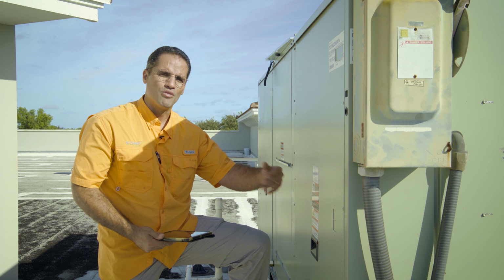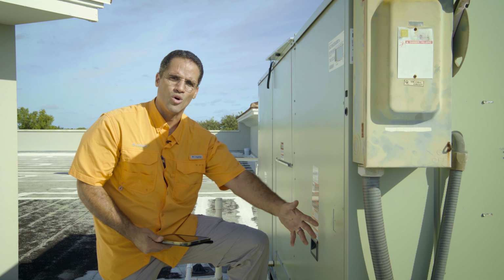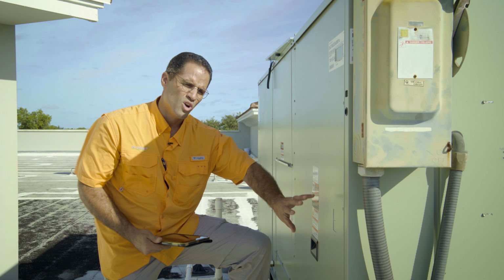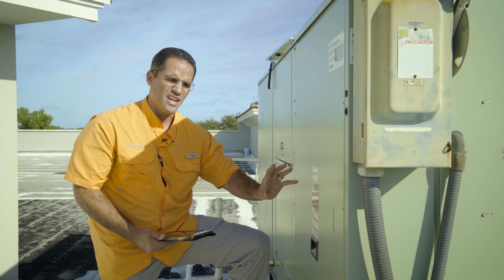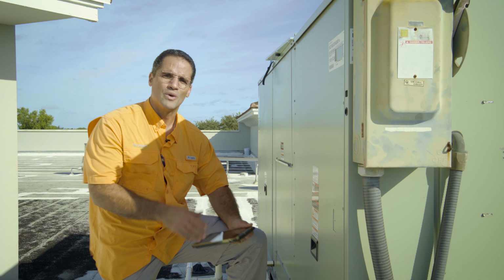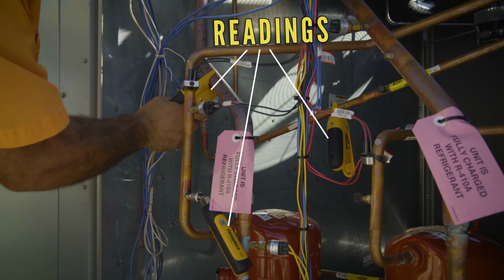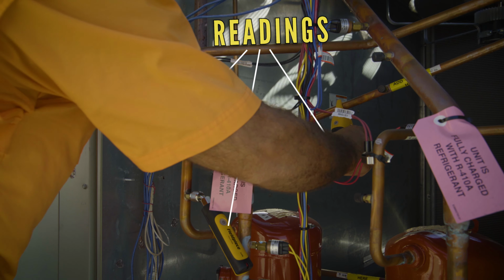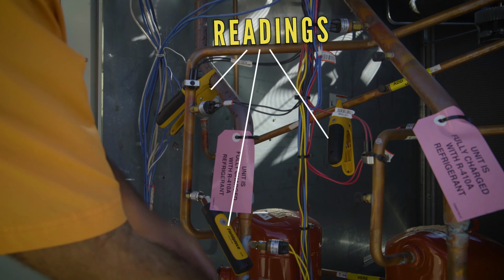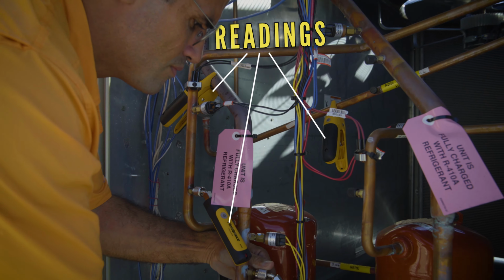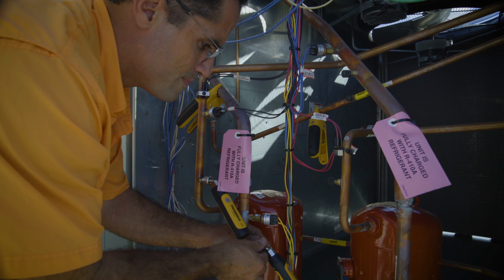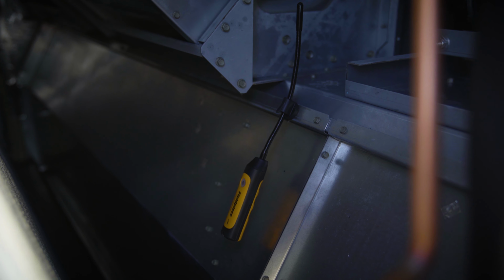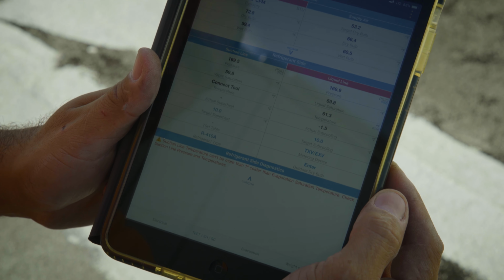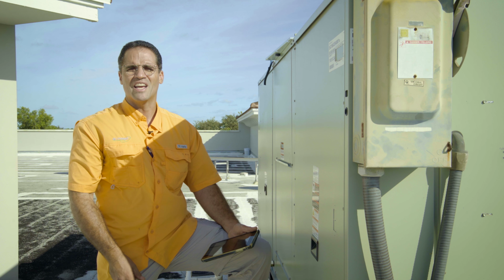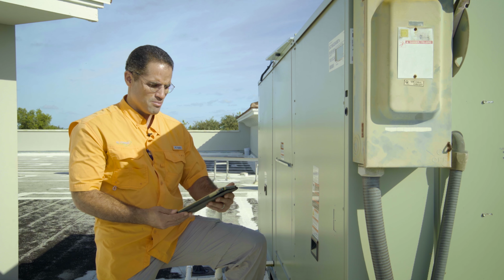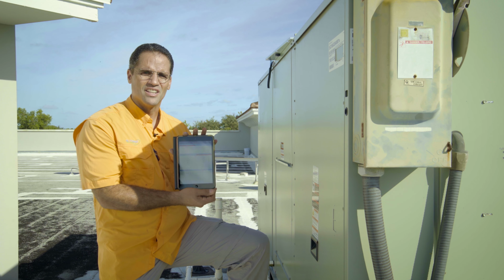Again, if we find anything that seems to be out of the norm, like oil pressure, I mean in regards to oil leaks, that's when we actually apply these gauges. But as of right now, we have the Fieldpiece connected. We're checking low pressure and high pressure refrigeration, and we're also checking the actual superheat and subcooling targets of the system, as well as entering and leaving air. And pretty much how it looks is just like this.